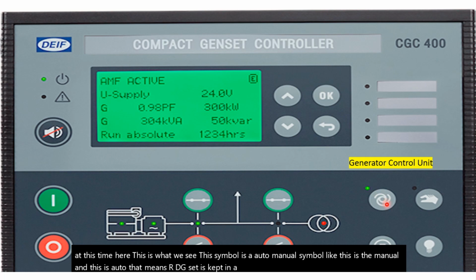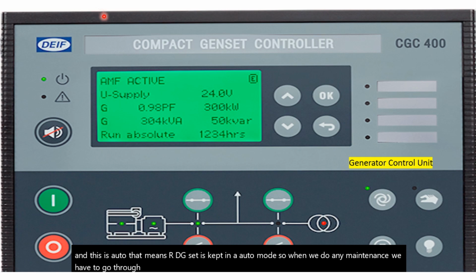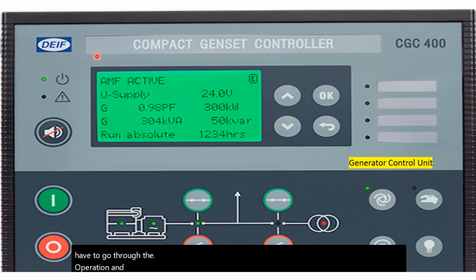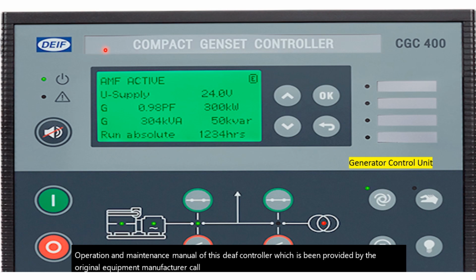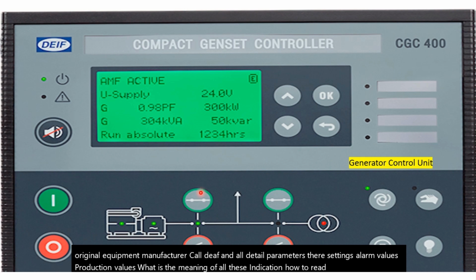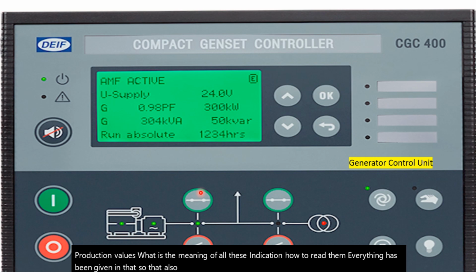When we do any maintenance, we have to go through the operation and maintenance manual of this controller, which has been provided by the original equipment manufacturer. All the detailed parameters, their settings, alarm values, protection values, the meaning of all these indications and how to read them, everything is given in it. So that also has to be referred to during the maintenance.